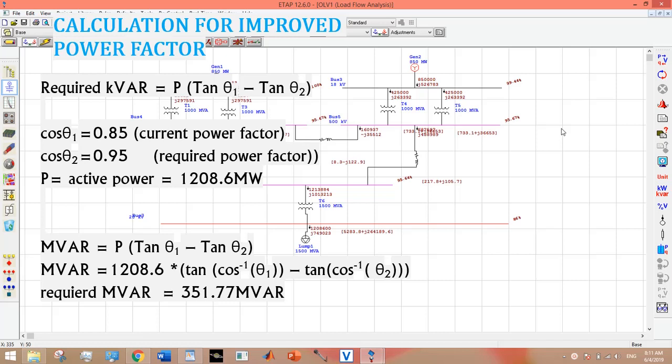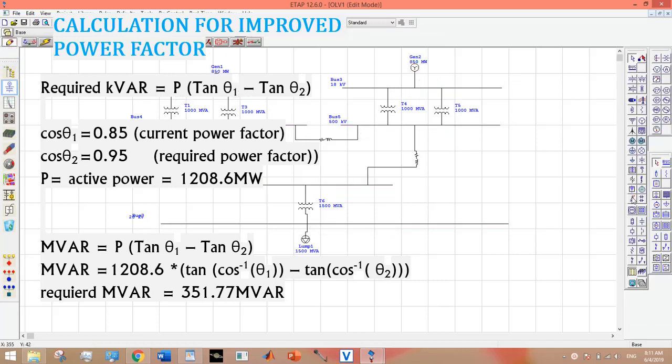My current active power is 1208.6 megawatts. My current power factor was 0.85, and I want it to be improved till 0.95. How I came to know it is 0.85: a very simple trick is that it is mentioned in the rating tab of load that power factor is 85% or 0.85.